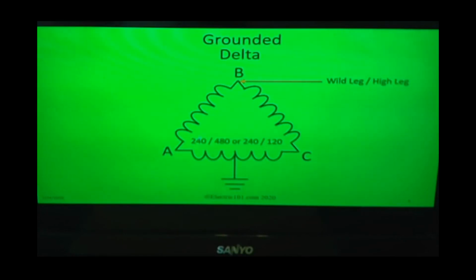If this is a 240 volt transformer, we measure 240 between any two phases. A to B, B to C, A to C, three-phase 240. Now if we ground it and create the neutral, we measure A phase to neutral, we get 120. We measure C phase to neutral, 120. We measure B phase to neutral, it gives you 208.